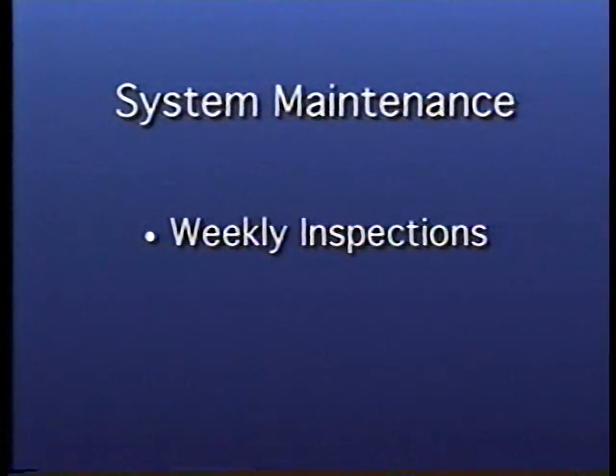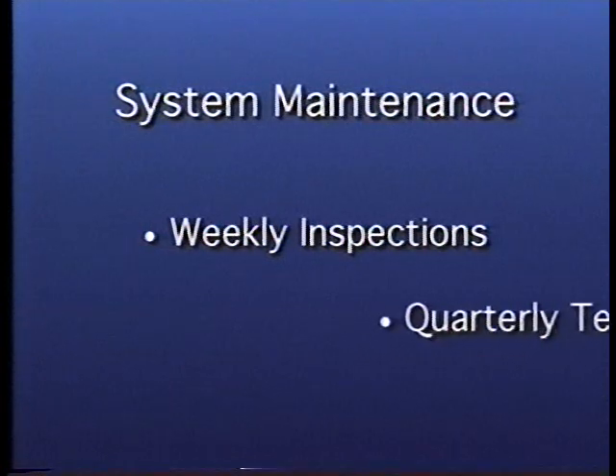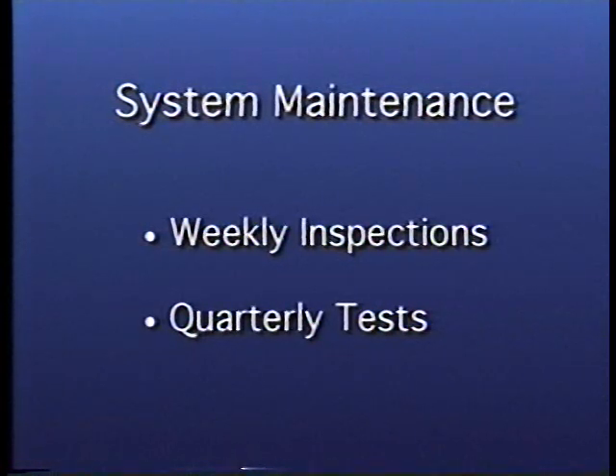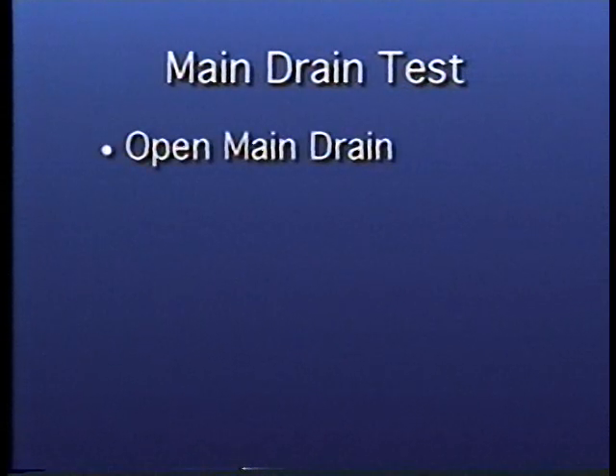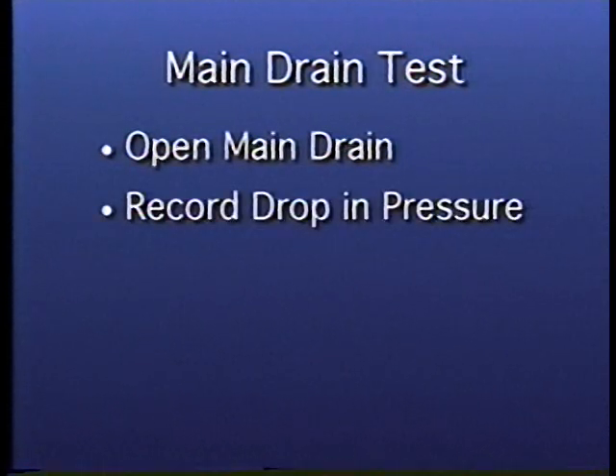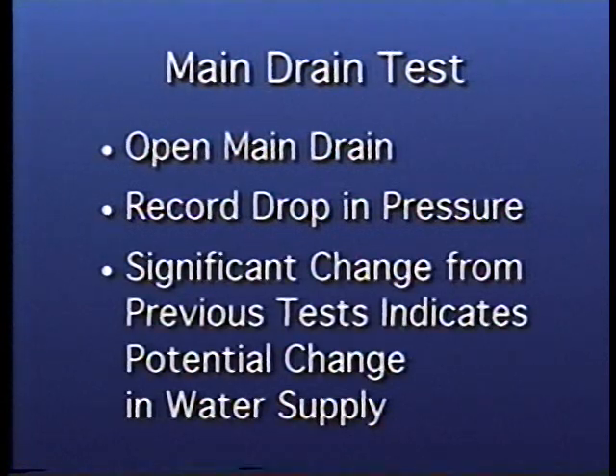Testing of the system's alarm devices and the main drain are to be conducted once each quarter. The purpose of the testing is to determine if the alarm device actually produces an alarm when water is flowed. The main drain test consists of opening the main drain to the sprinkler system and observing and recording the drop in pressure. Any significant change in the pressure drop from previous tests indicates a potential change in the water supply to the sprinkler system. That change should be evaluated to determine if the effect would degrade the performance of a system in an actual fire emergency.